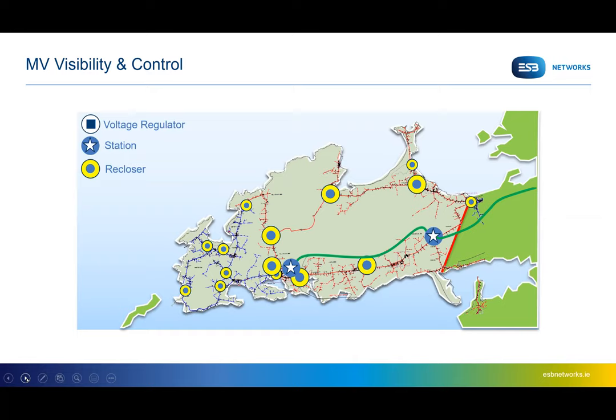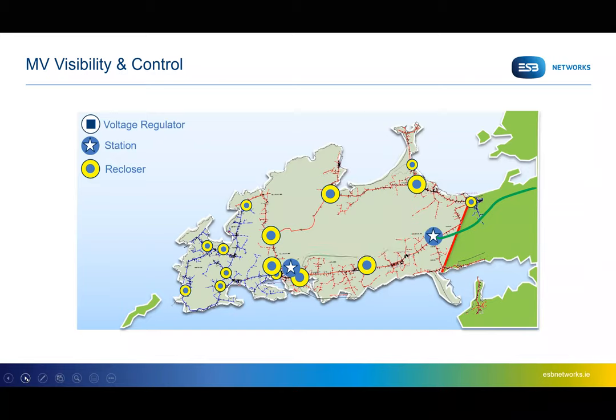As part of our project, we worked with the people out of the Tralee area to upgrade a lot of the technologies on the peninsula, in particular the recloser devices on the 20 kV network. These are really important and helpful to automate the switching and backfeeding during maintenance work on the 38 kV stations or the circuit between the two stations, as I showed. If you look at the yellow circles on the 20 kV network, we've upgraded 5 of the 6 reclosers, and they're now fully controllable from the National Distribution Control Center.